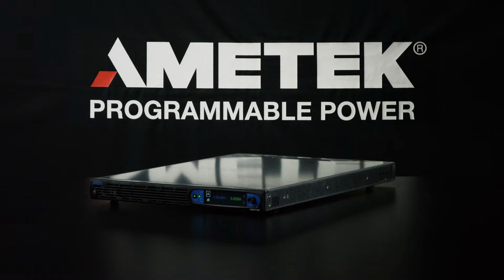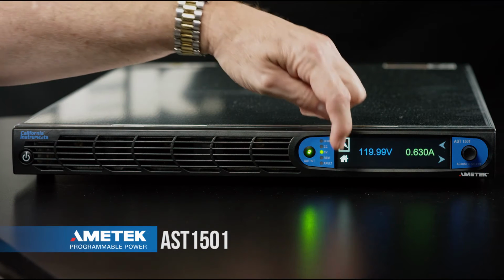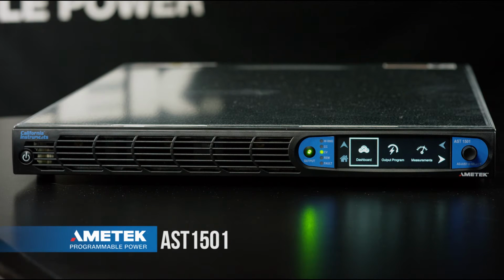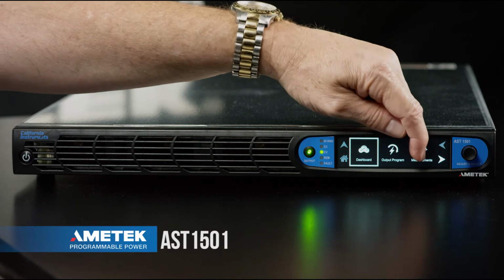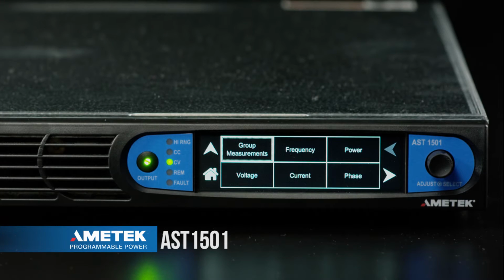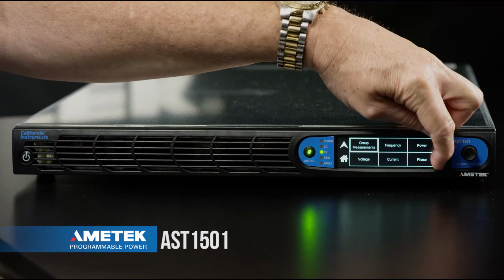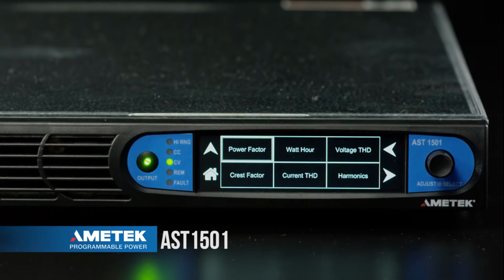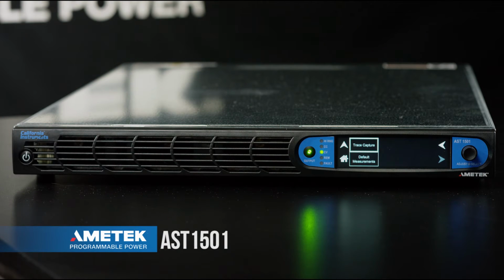Next, we're going to use measurements. From the static display, we're going to select our home screen. Next, we're going to select measurements. From measurements, we can select a number of parameters to measure voltage, current, frequency, power, phase. Select the right menu key, power factor, watt hour, voltage distortion, crest factor, current distortion, and harmonics, as well as do a trace capture and set our default measurements.